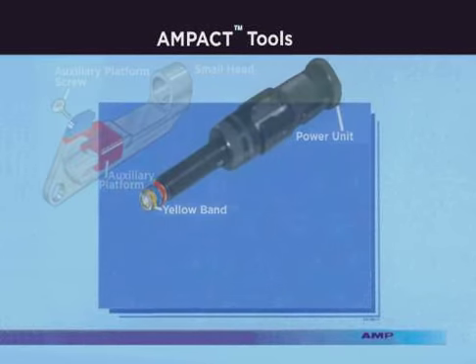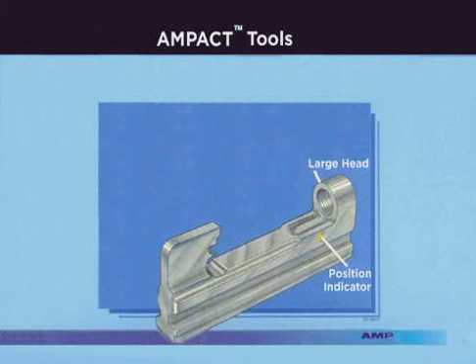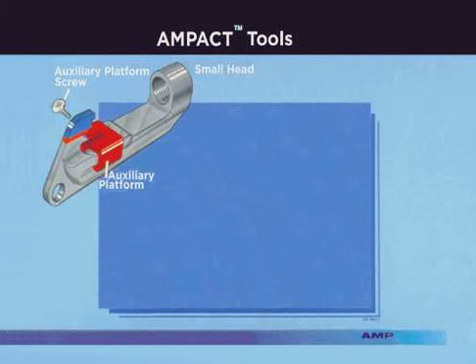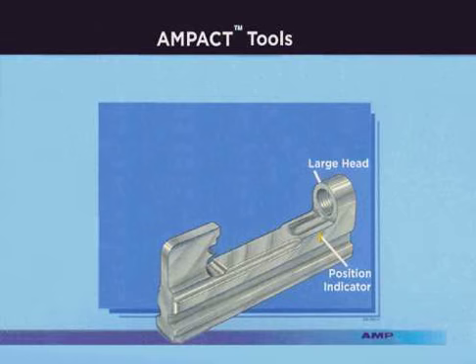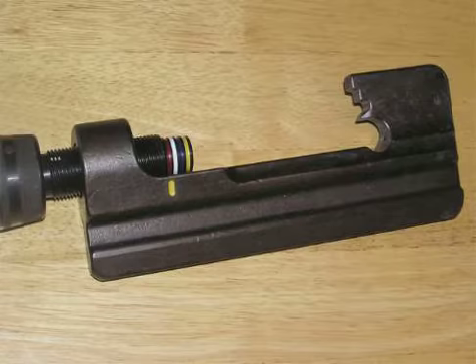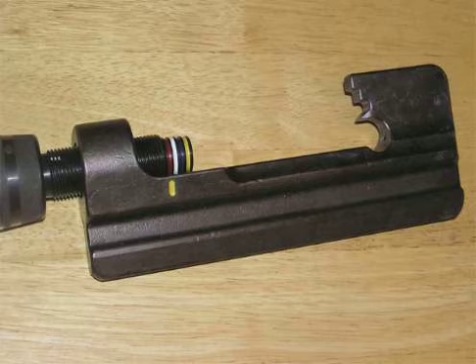The AMPACT application tool consists of two components: the head and power unit. Two types of heads are available — small and large. The small head is used to apply small red coated taps and medium blue coated taps, as well as the copper and type 2 taps. The large head is used to apply the large yellow coated taps. Both heads are interchangeable with the power unit, however they are not available separately.